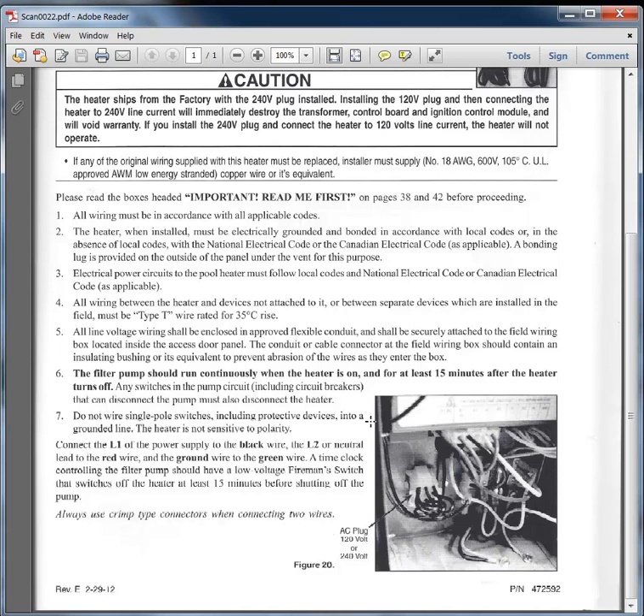If you have a time clock, it has to be specially made so that it has a fireman switch, where it turns off this heater 15 minutes prior to turning off the pool pump. So if you have a regular timer disconnect, and it shuts off your pool pump and STA-RITE heater at the same time, it could cause you to void your warranty.